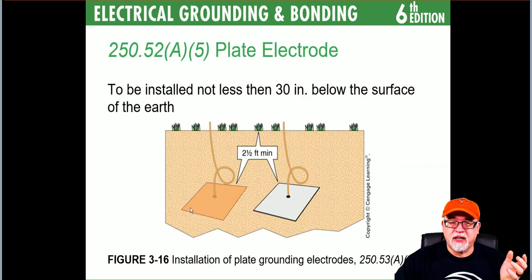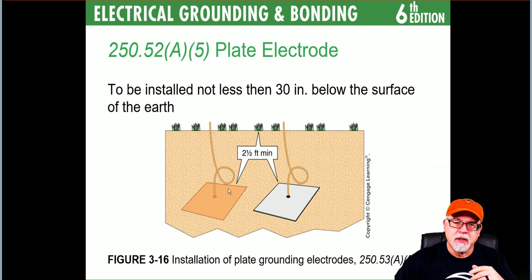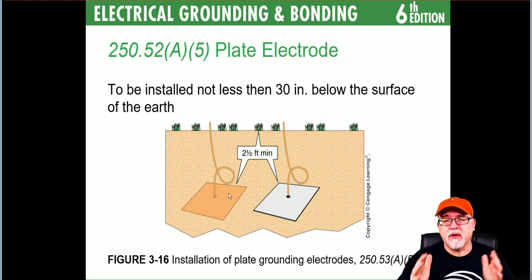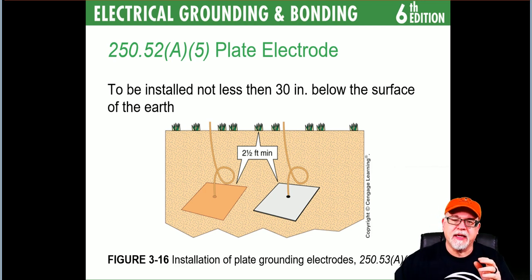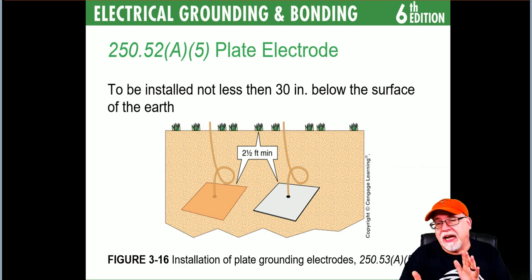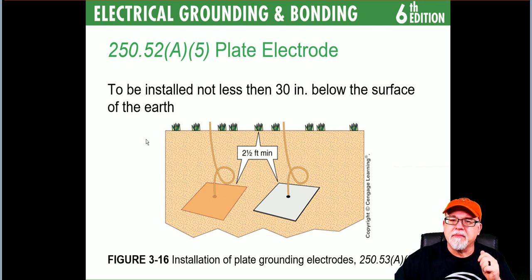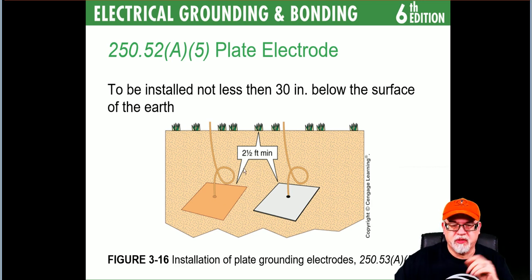Plates can't be less than 30 inches below the surface and must have two feet of surface area in contact with the earth. A one-foot by one-foot plate provides one square foot per side — using both sides gives two square feet of contact area. The code requires a minimum of two feet of surface area and a minimum burial depth of two and a half feet, which equals 30 inches.